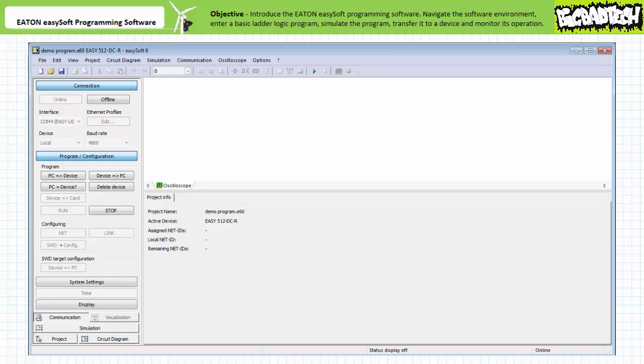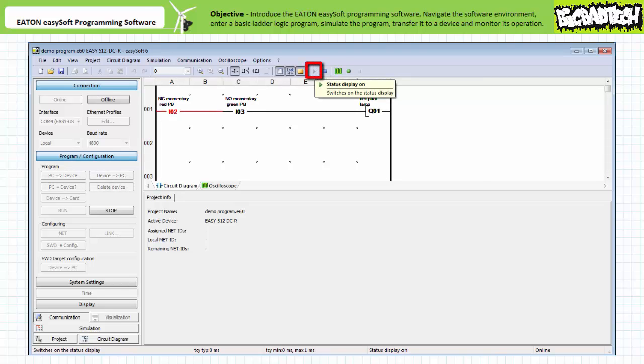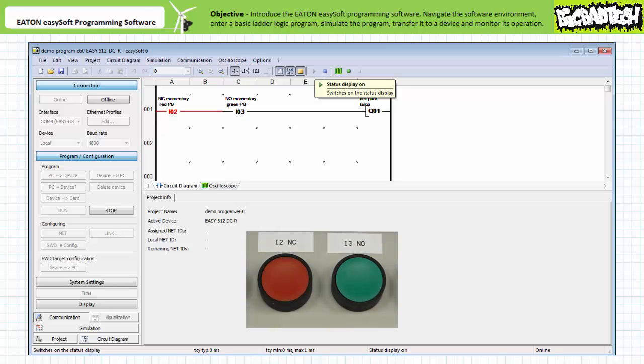Note, while connection is established to an actual device containing a valid program, one can remotely control and monitor the device's response to real-world field input devices. To do so, one must press Run and the Status Display button. The Status Display is this program's means of remotely monitoring an actual system in operation. Note, when neither button is actuated, the remote monitoring utility indicates the make instruction examining I2 permits logical continuity. However, I3 does not permit logical continuity onto the output and output coil Q1 is de-energized. The remote monitoring utility symbolizes logical continuity by highlighting the active portion of a rung in bold red.